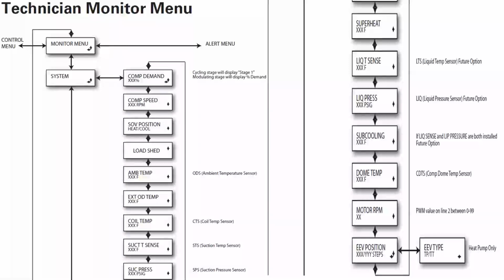3 to 5 minutes under 32 volts DC. Okay, Jeremy's got you. Dome temp, that's our compressor dome temp. I like to confirm that dome temperature sensor is secured, fastened onto the liquid discharge line on the compressor. I have seen those rattle off.